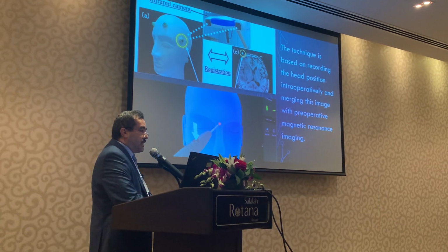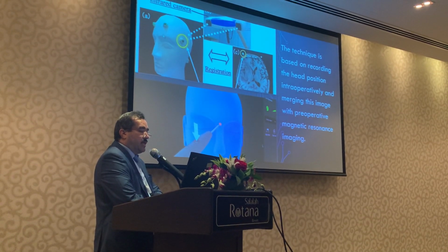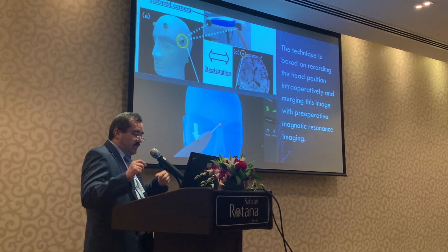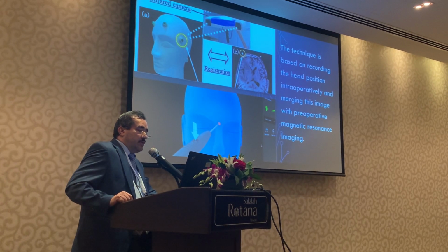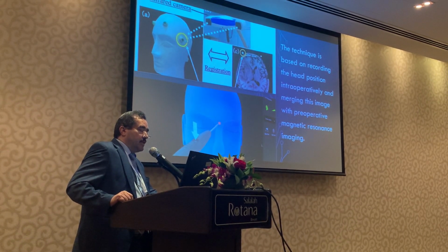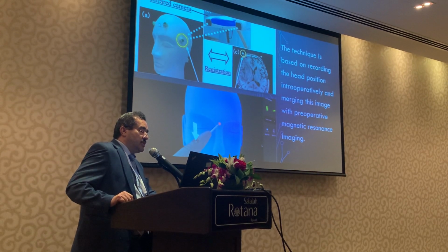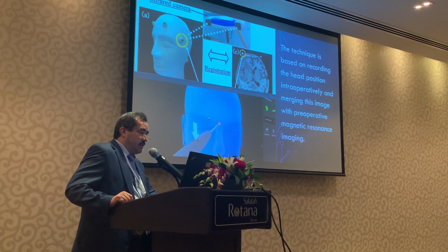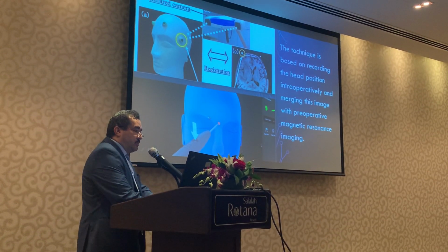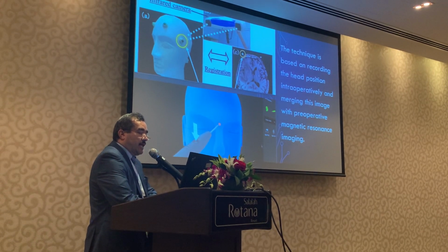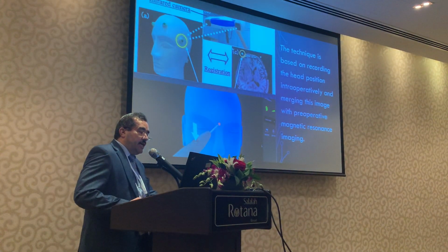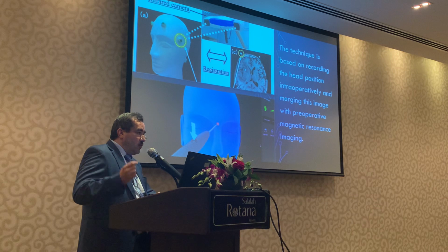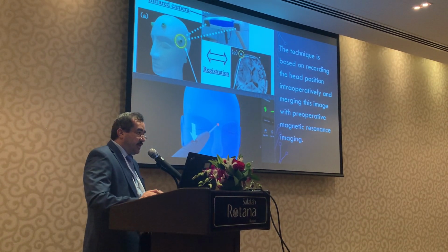The whole system depends on what we call registration of the patient's head. You should make a 3D image of the head, and by registration we use either infrared cameras with fiducials, which are marks detected by the infrared, or a laser pointer. When we draw this 3D head position, we take an MRI and fuse the head position with the MRI picture, so that for anything I use, I know through the MRI where I am inside the brain.